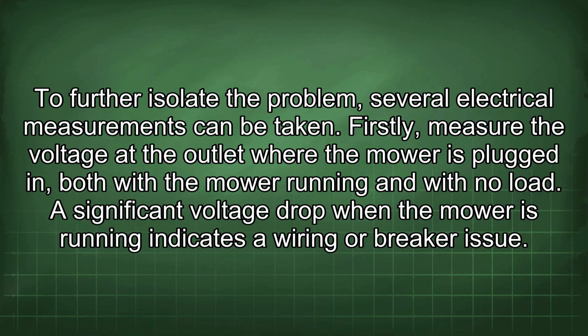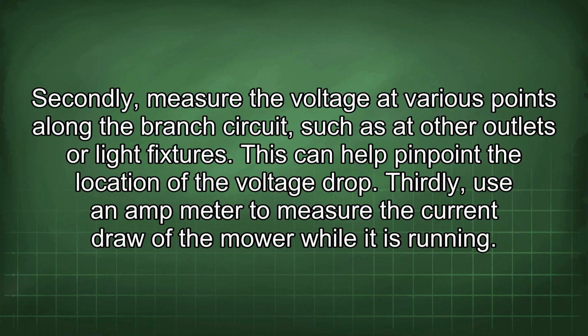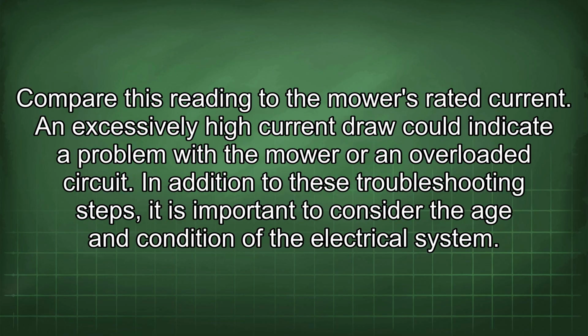Firstly, measure the voltage at the outlet where the mower is plugged in, both with the mower running and with no load. A significant voltage drop when the mower is running indicates a wiring or breaker issue. Secondly, measure the voltage at various points along the branch circuit, such as at other outlets or light fixtures. This can help pinpoint the location of the voltage drop. Thirdly, use an amp meter to measure the current draw of the mower while it is running. Compare this reading to the mower's rated current. An excessively high current draw could indicate a problem with the mower or an overloaded circuit.